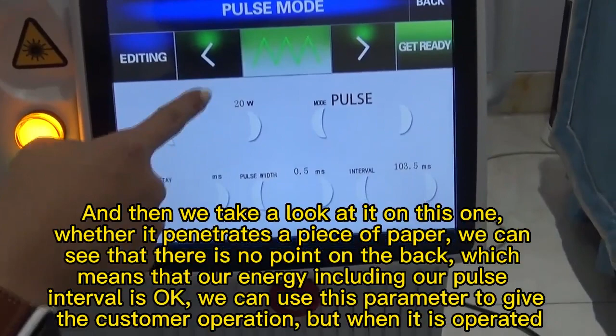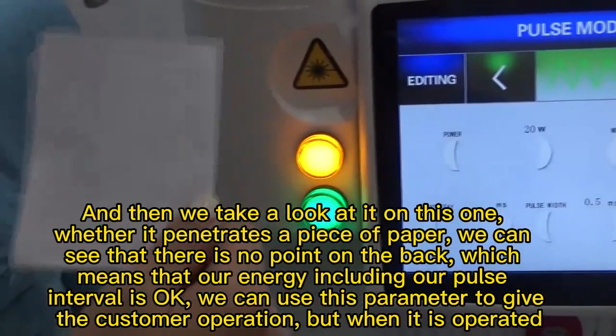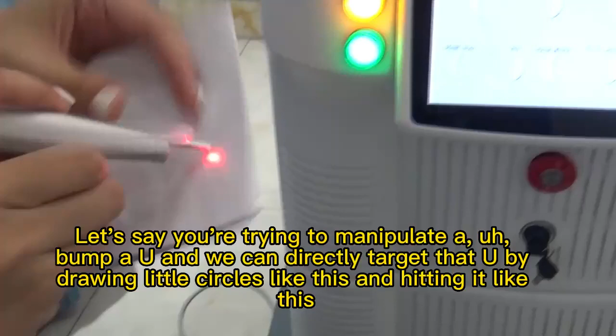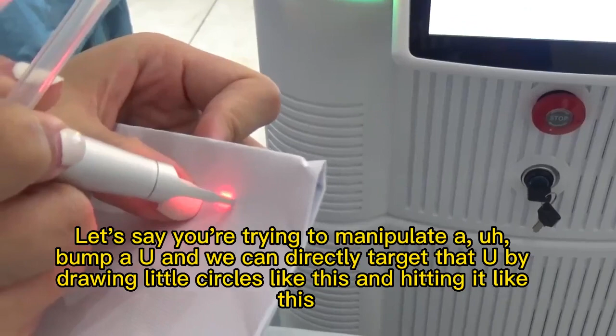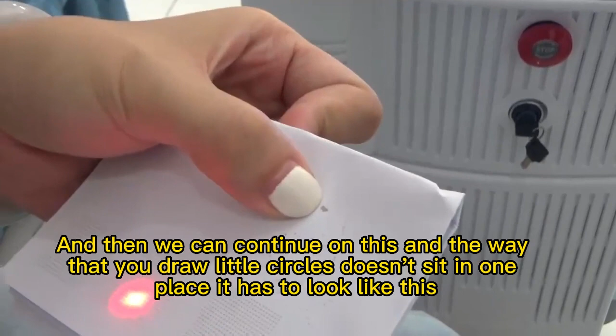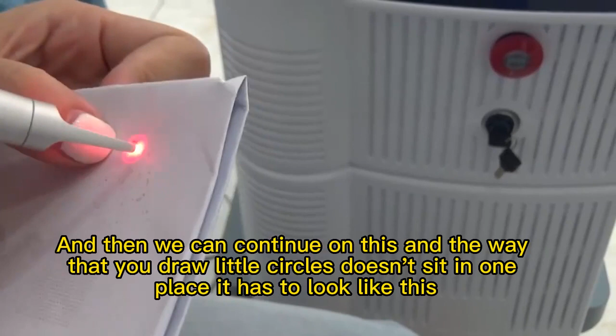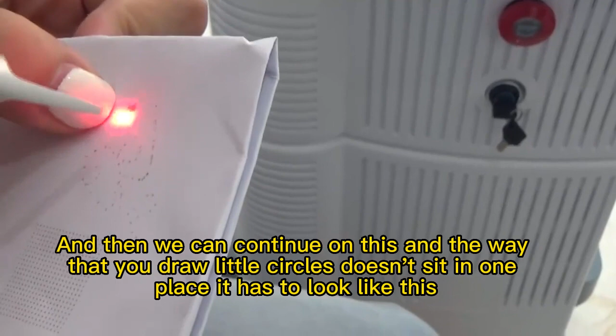After we step on the middle layer of the foot switch, step on and do not release. At the same time, we need to move this probe. You can see that there are a lot of little black dots on it, and you can hear a rattling sound, which means we're on the right pattern. And then we take a look at whether it penetrates a piece of paper. We can see that there is no point on the back, which means that our energy including our pulse interval is okay. We can use this parameter to give the customer operation.